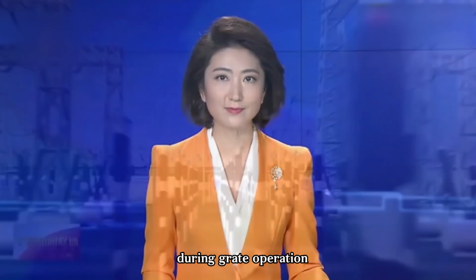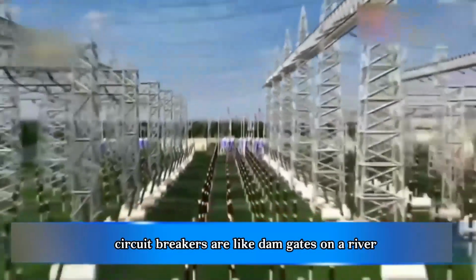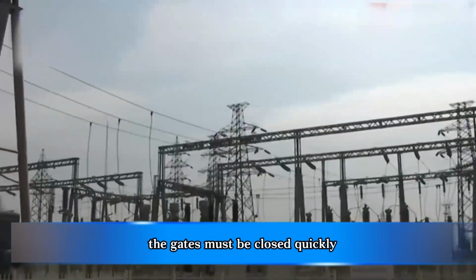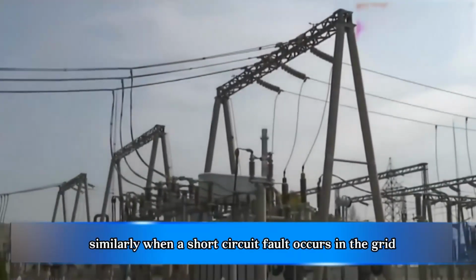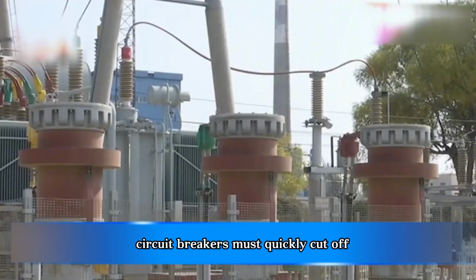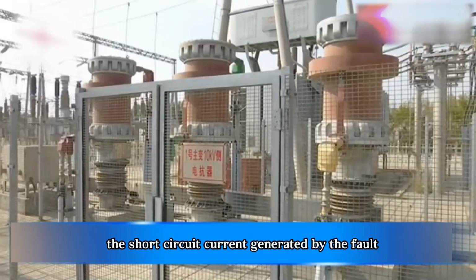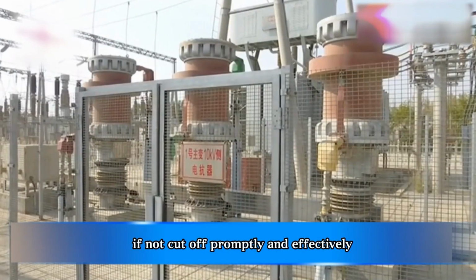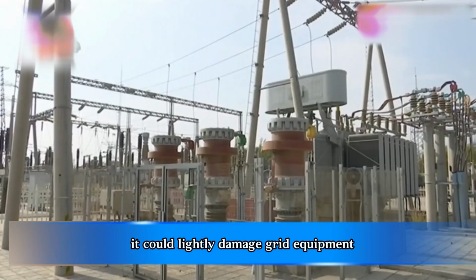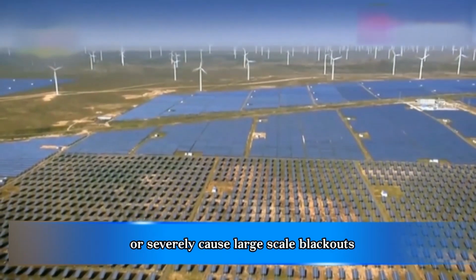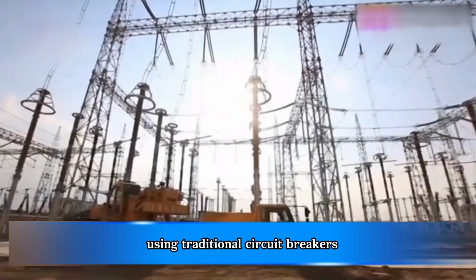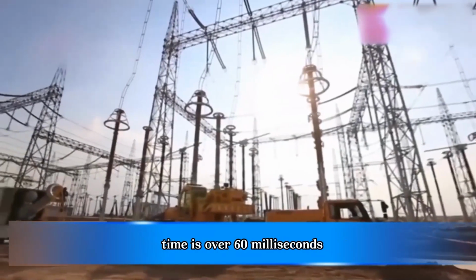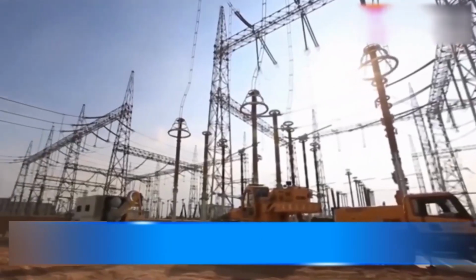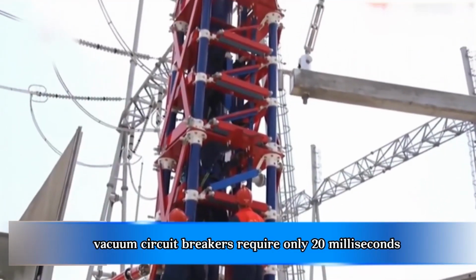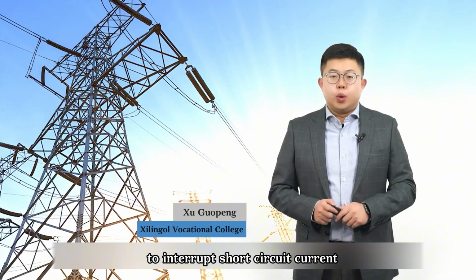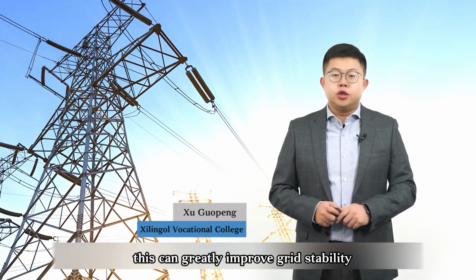During grid operation, circuit breakers are like dam gates on a river. When flooding occurs downstream, the gates must be closed quickly. Similarly, when a short circuit fault occurs in the grid, circuit breakers must quickly cut off the short circuit current generated by the fault. If not cut off promptly and effectively, it could lightly damage grid equipment or severely cause large-scale blackouts. Using traditional circuit breakers, the short circuit current interruption time is over 60 milliseconds. However, fast vacuum circuit breakers require only 20 milliseconds to interrupt short circuit current. This can greatly improve grid stability and power quality.